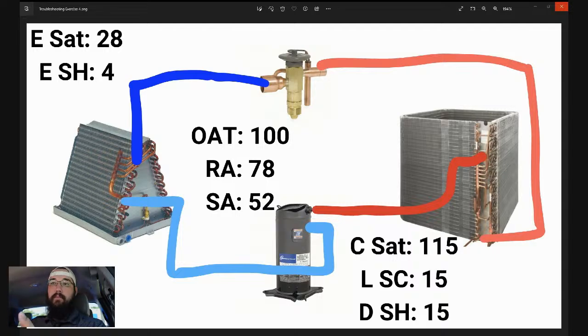And this is a pretty common scenario to run into where the coil itself just doesn't look that bad. You wouldn't think the coil would be that big of an issue, but once you actually get in there and start addressing it, you learn that it is. So at that stage, if you have the ability, if it's a scenario where you can pull the coil and clean it, great. A lot of times we don't have that luxury.